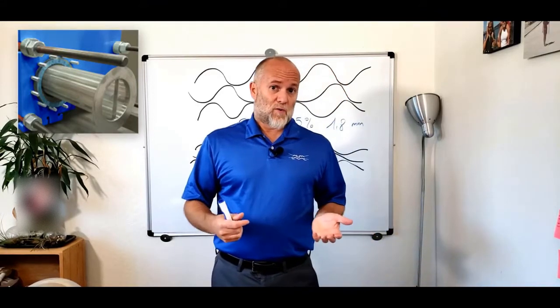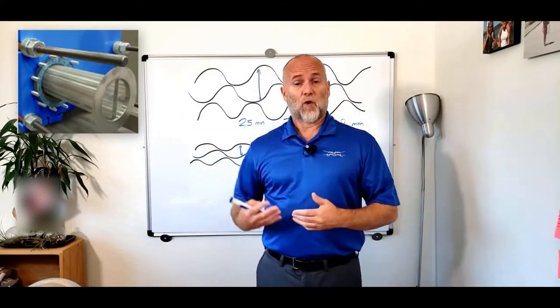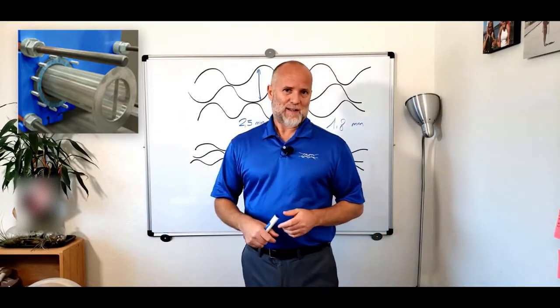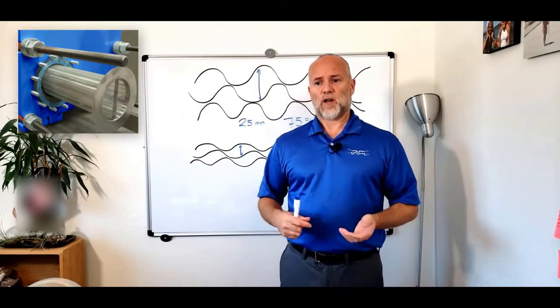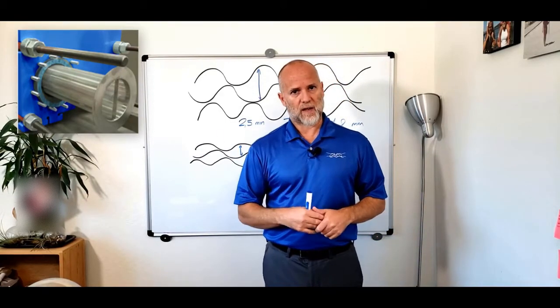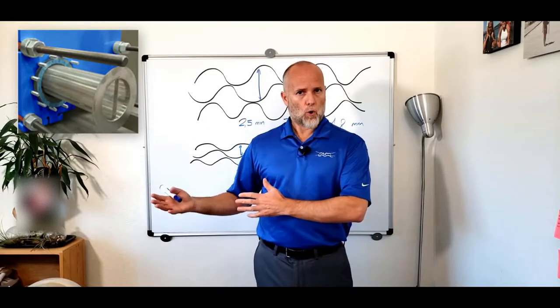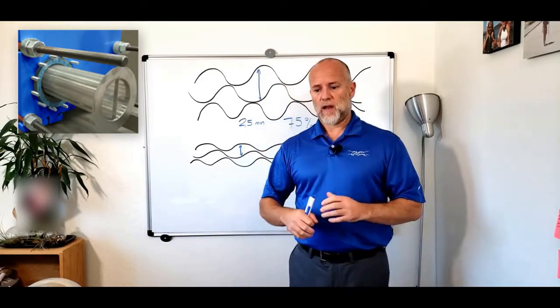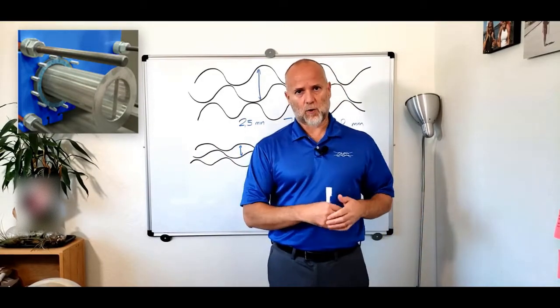In theory you can have port filters in the four ports, but it doesn't really make sense. You want port filters normally only in the inlet of the cold water coming from the cooling tower or from the chiller, in any case the cold inlet.